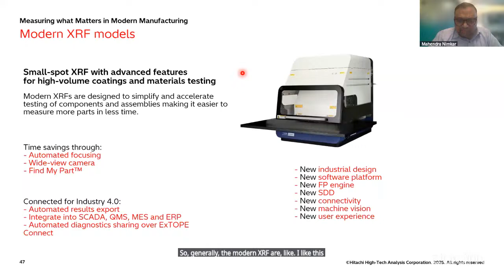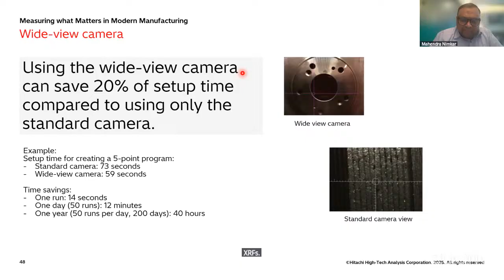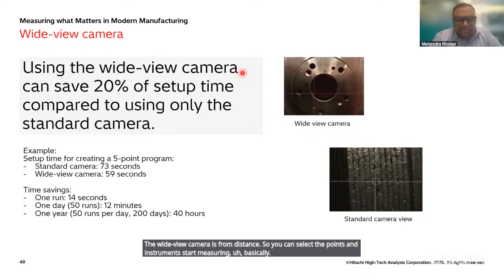So what is the advantage of the wide view camera? For example, if you have an XYZ stage and you want to run analysis on 5 different points, you can quickly set those 5 points with a wide view camera. Earlier, there used to be only one single camera, a big camera, but with a wide view you can select the points and run the analysis very quickly compared to the standard or earlier XRFs. The standard camera view was very close. The wide view camera is from a distance, so you can select the points, and the instrument starts measuring those points for thickness.